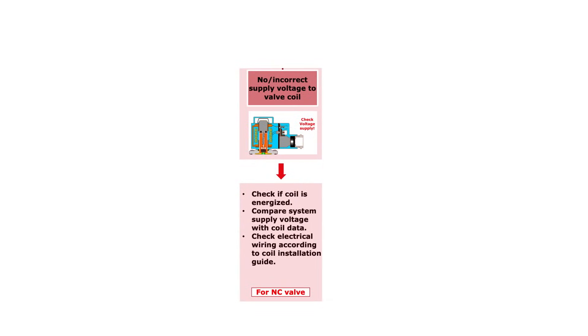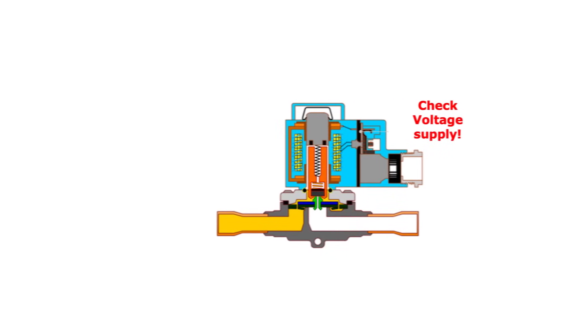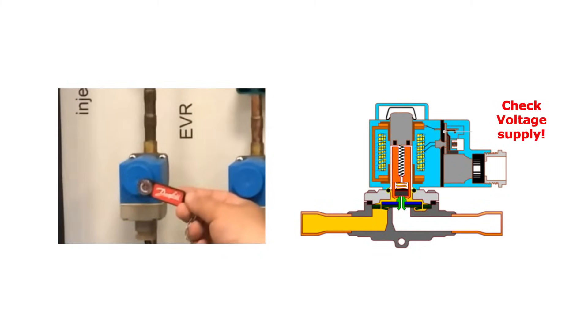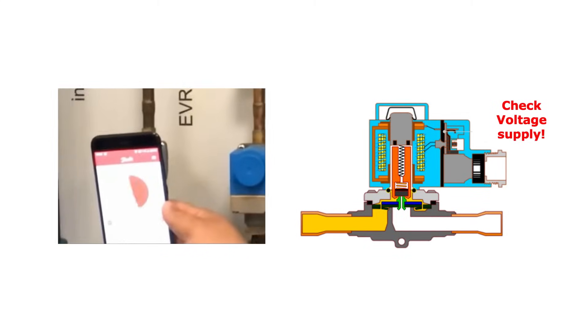If there seems to be no supply voltage to the coil, or maybe incorrect supply voltage causing the valve not to open, then the first step is to check if the coil is energized by any supply voltage. This can be done by using the Danfoss Magnetic Field Detecting Keyring, as seen here, or the Danfoss Magnetic Tool App, as seen here.